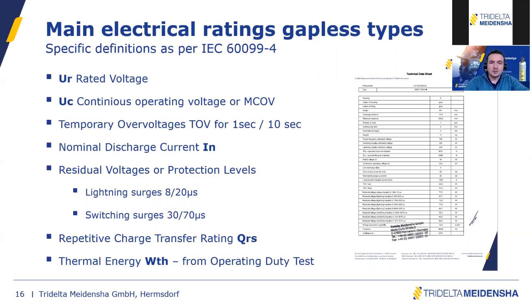Here I just want to show the typical ratings for gapless arresters according to IEC 60099-4. The rated voltage and the continuous operating voltage, UC, are the important ratings if you want to specify surge arresters. We also have the temporary overvoltage, TOV, for 1 or 10 seconds. We have a nominal discharge current. When you see a nominal discharge current, sometimes 10 kA, sometimes 20 kA, it's not related to the performance of the arrester. It's only used for classification.